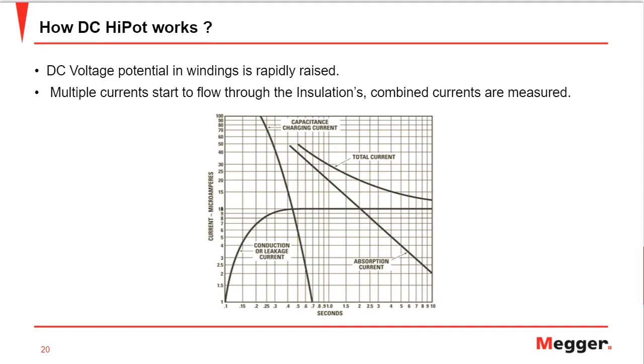The first one is the capacitance current, which is also called the inrush current because of the capacitive nature of the windings. This current typically drops to zero within seconds. Next is the absorption current, which is usually present when we are doing a megohm test at the rated voltage of that motor. This current will drop to zero after some time. The third one is the conduction or leakage current, often referred to as surface leakage current, and the surface conduction current runs over the end winding surfaces of the insulation. Combining all these currents, the high-pot tester measures the total current to determine the linearity of the DC high-pot result.